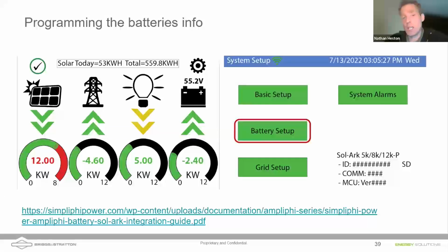That's a good question. There's very little change in lithium iron phosphate batteries with temperature. If I were to show you a graph of what the resting voltage looks like as a function of temperature, there's almost no change. That temperature compensation is mostly for lead acids. I think the answer is yes, although I'd have to defer to Sol-Ark to make sure. But I believe that the temperature compensation can be set to 0.